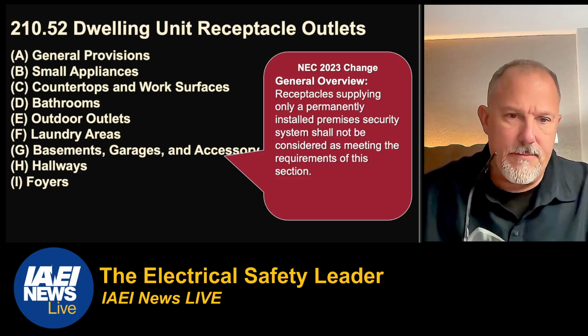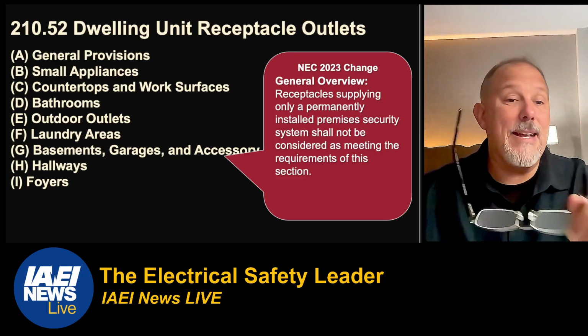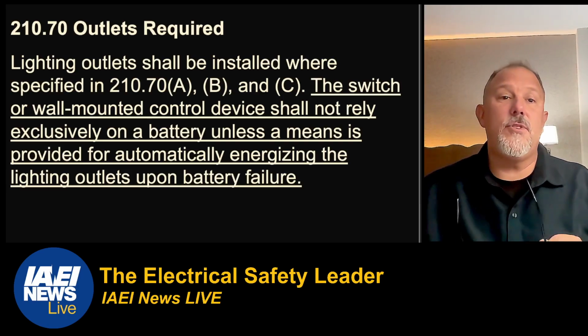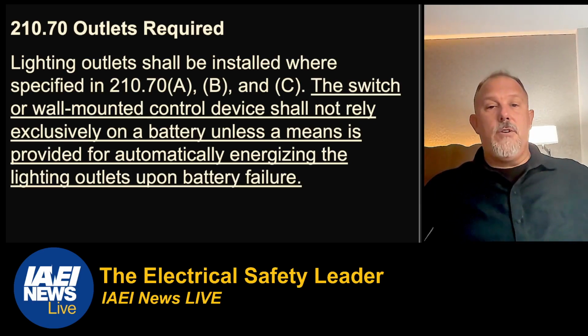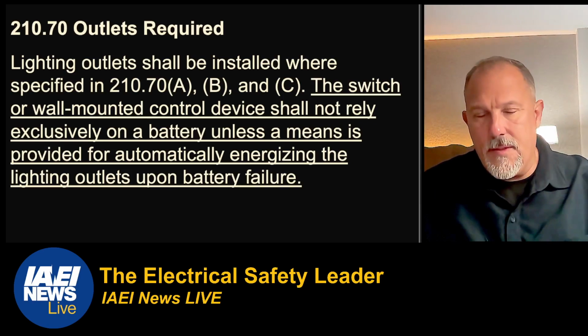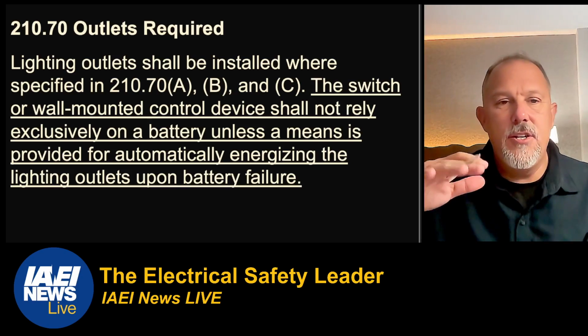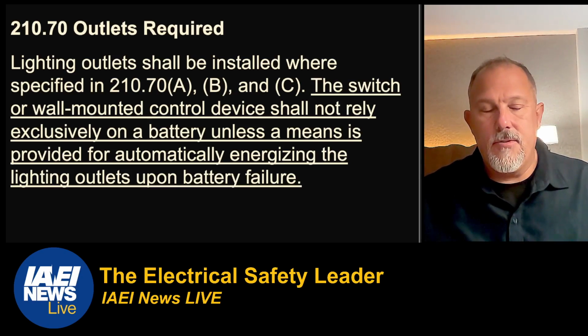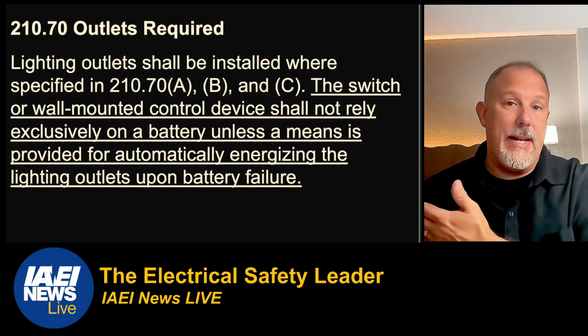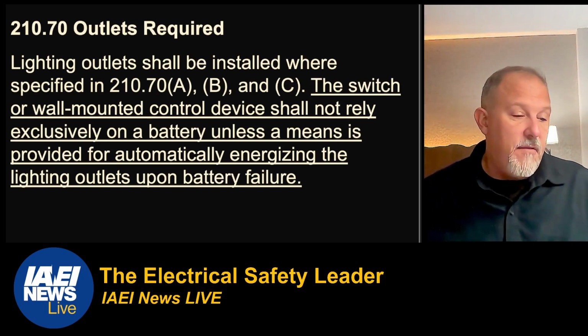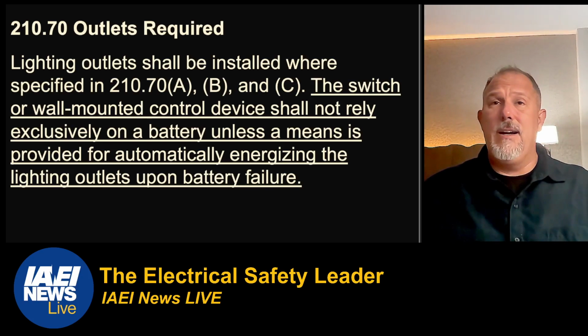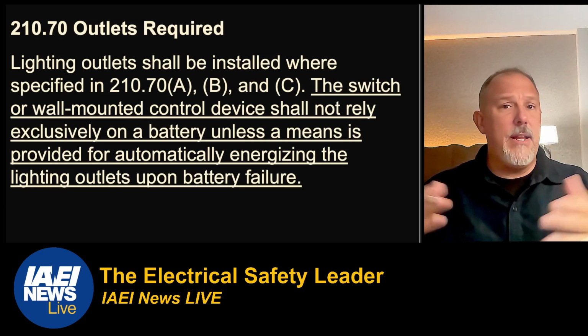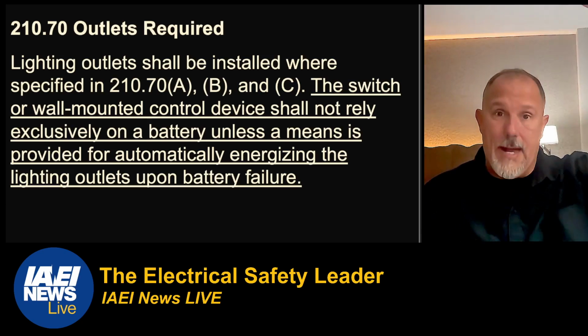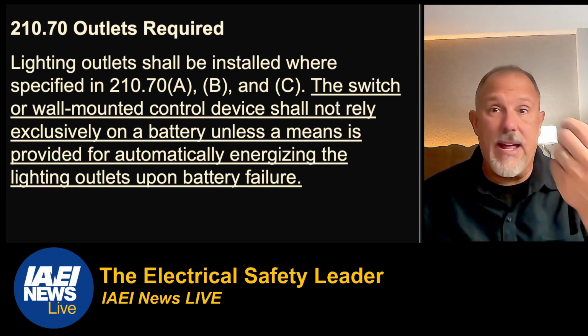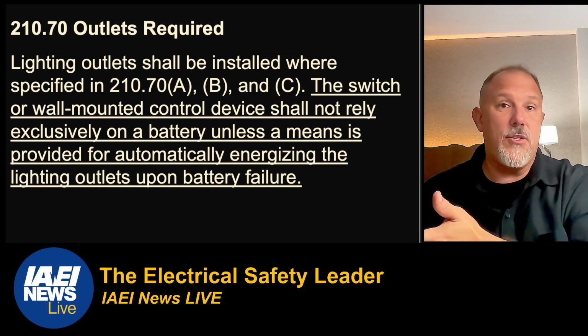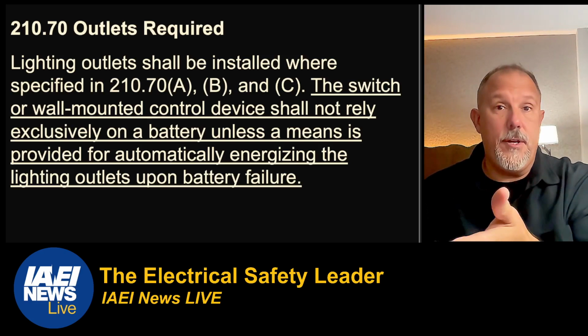But it didn't change. So anyway, the last one we're going to hit is lighting. So 210.70, lighting outlets shall be installed. And now one of the terms that we added last cycle was this switch or wall mounted control device. Remember, this is like those wireless controllers for lighting. And the concern of people on the panel was, well, I may be able to, in any of my installations, not pull wire down to a lighting switch, where I have a physical wire that, if I want to go back to a standard light switch, I could.